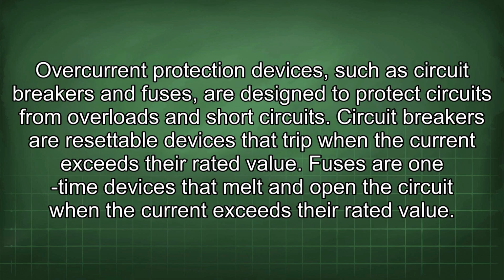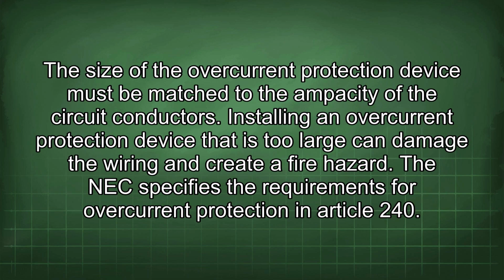Overcurrent protection devices, such as circuit breakers and fuses, are designed to protect circuits from overloads and short circuits. Circuit breakers are resettable devices that trip when the current exceeds their rated value. Fuses are one-time devices that melt and open the circuit when the current exceeds their rated value. The size of the overcurrent protection device must be matched to the ampacity of the circuit conductors. Installing an overcurrent protection device that is too large can damage the wiring and create a fire hazard. The NEC specifies the requirements for overcurrent protection in Article 240.